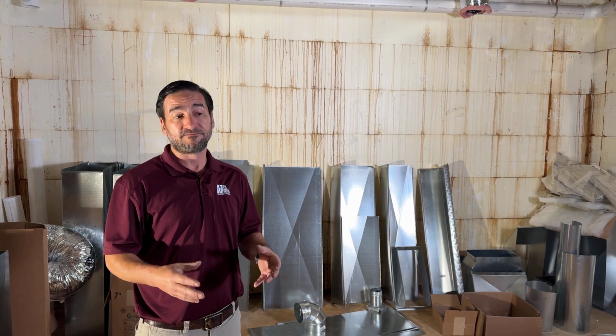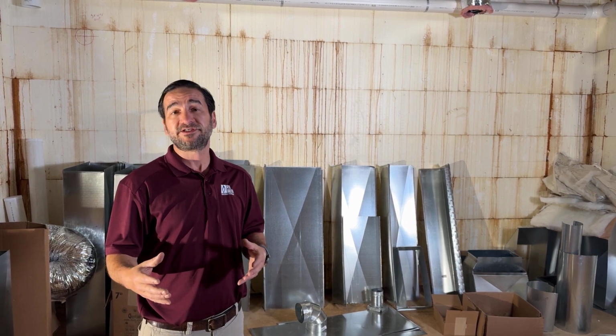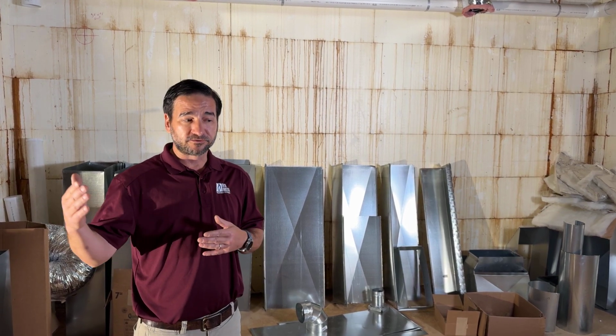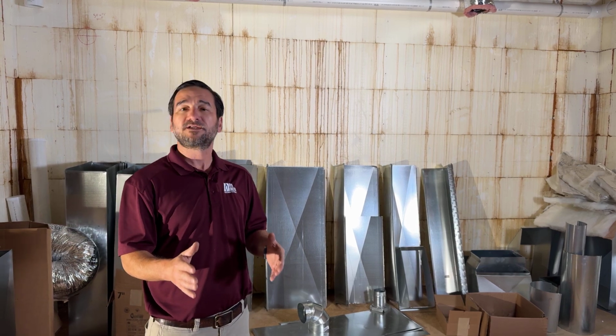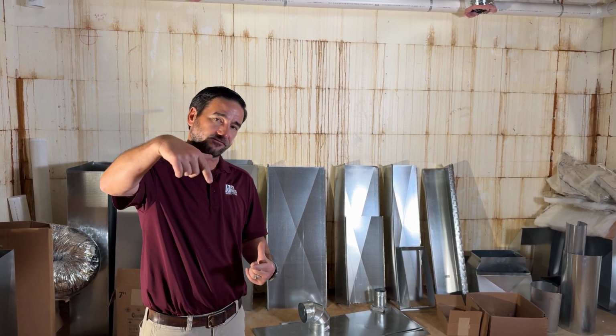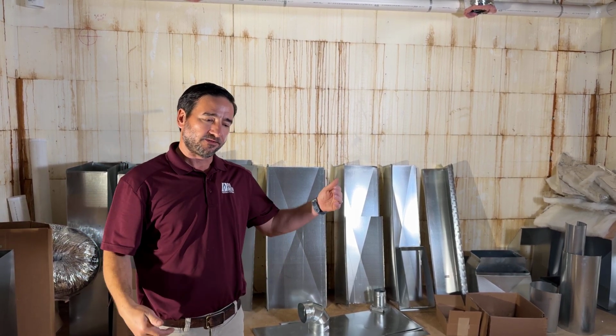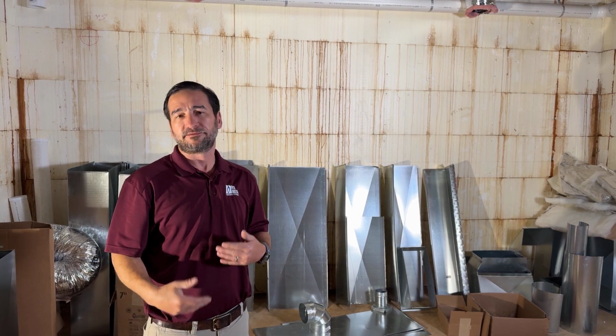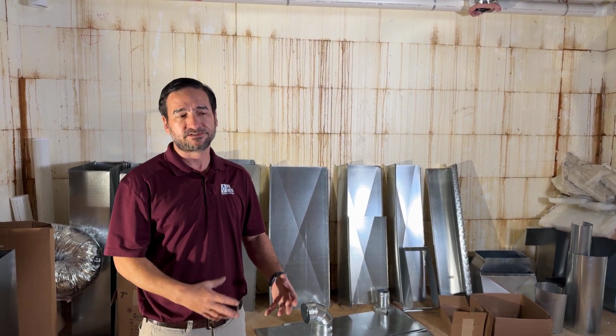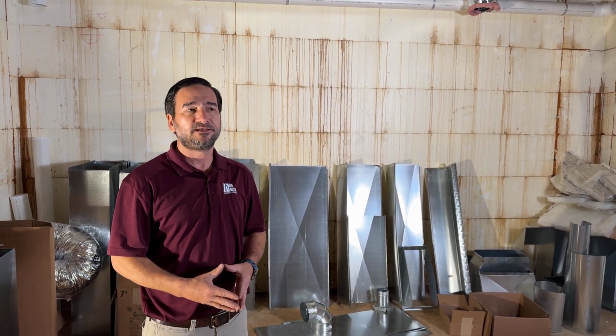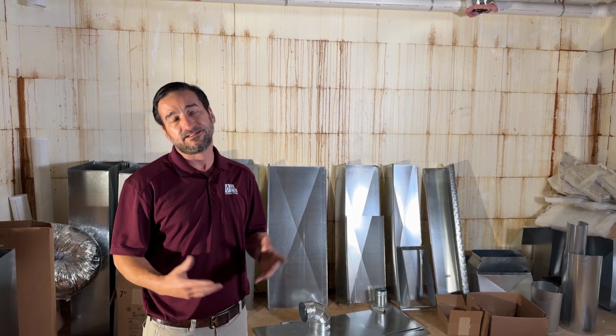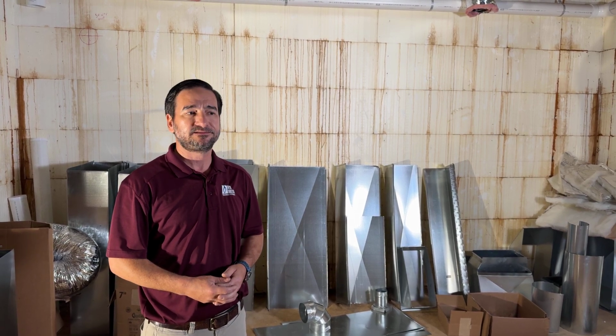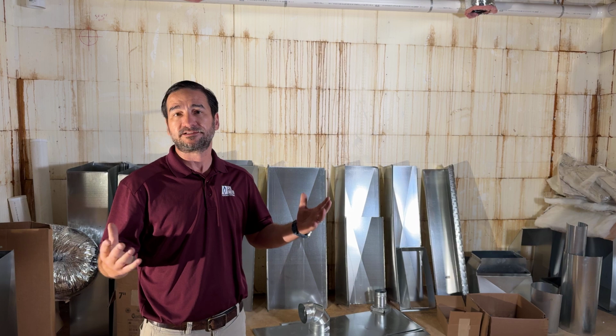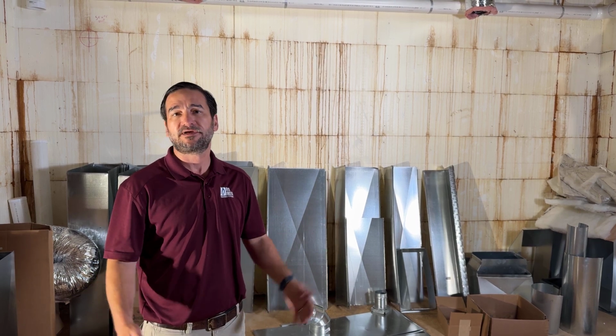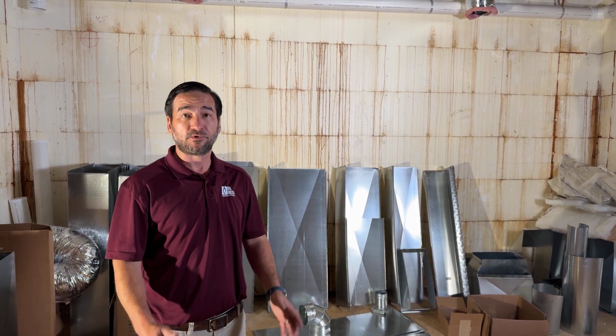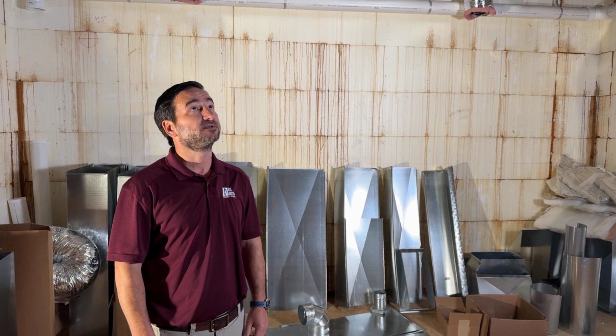Other benefits of a multi-stage system is you're getting more out of your filtration system too. When your unit is moving a lower quantity of air across your filter surface area, the slower the air moves across that filter, the better job it can do also. So there's lots of benefits. Of course it costs more, but in today's day and age, it's not twice. It's probably 20% or 25% more for a good multi-stage equipment or system.